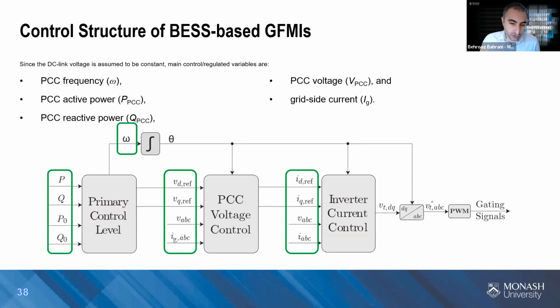When controlling your battery energy storage system based grid forming inverters, there are a number of variables to control. Essentially, you control real and reactive power using a primary control loop. This primary control loop gives you the frequency for your control system, unlike grid following inverters that require a PLL to do so. You've got PCC voltage control, which receives references from the primary loop and generates the current references for your inverter current control loop. These are the variables you typically use to control your battery energy storage system based GFMIs, and there aren't many of them.